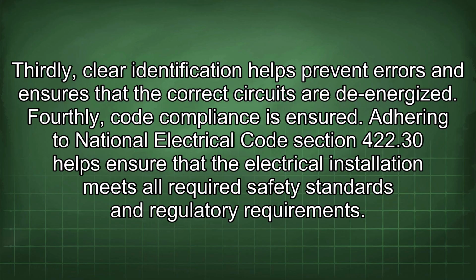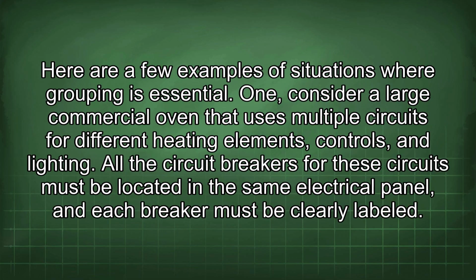Fourthly, code compliance is ensured. Adhering to National Electrical Code Section 422.30 helps ensure that the electrical installation meets all required safety standards and regulatory requirements. Here are a few examples of situations where grouping is essential. 1. Consider a large commercial oven that uses multiple circuits for different heating elements, controls, and lighting.